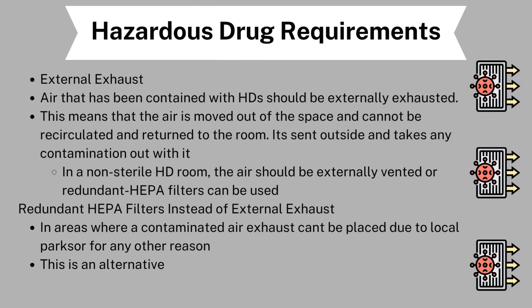When handling hazardous drugs, the pharmacy needs an external exhaust. Air that has been contaminated with hazardous drugs should be externally exhausted, meaning the air should go out of the pharmacy. The air is moved out of the space and cannot be recirculated or returned to the room — it is sent outside and takes any contamination with it in a non-sterile hazardous room.